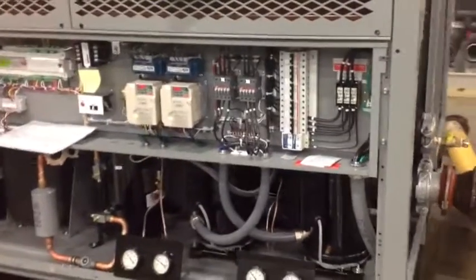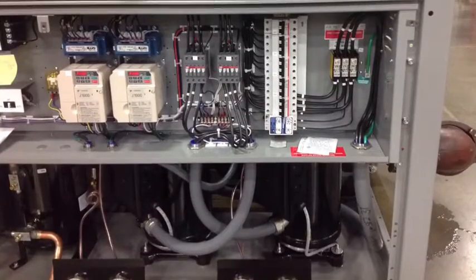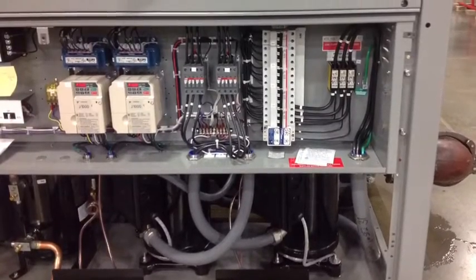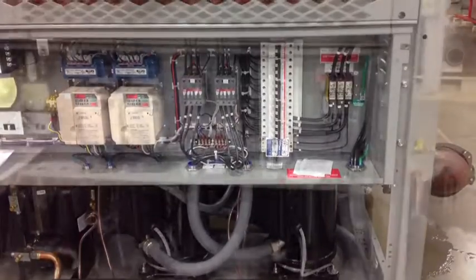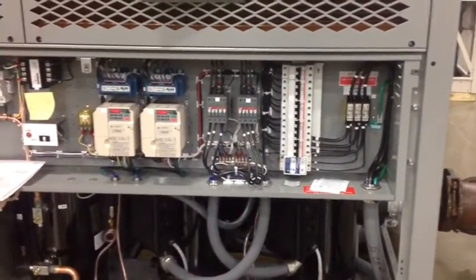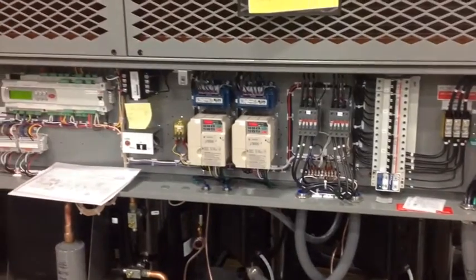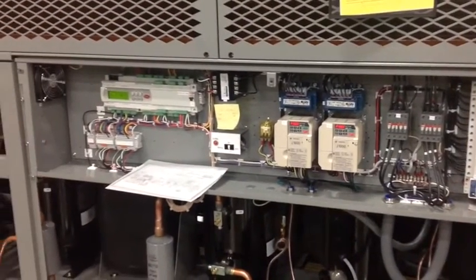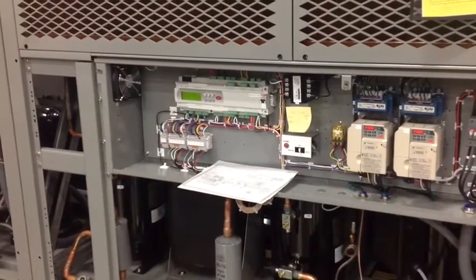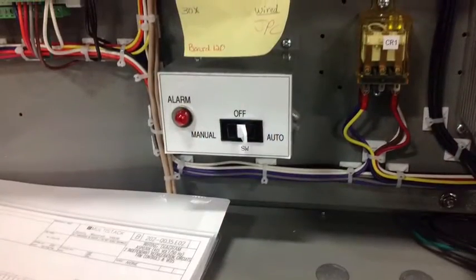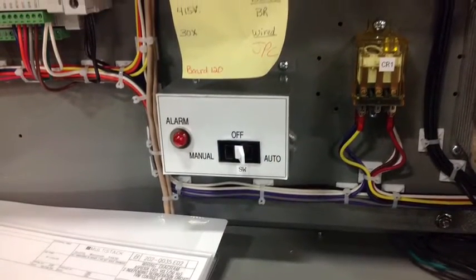Power comes in on the right-hand side of the cabinet and works its way right to left through a power distribution block, breakers for control power, the 2 condenser fans, and the 2 compressors. In the lower part of that breaker stack is the power phase monitor. You can see the VFDs for the condenser fans and the manual off auto switch in this close-up view.